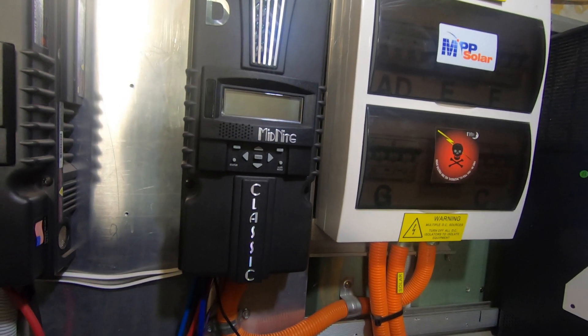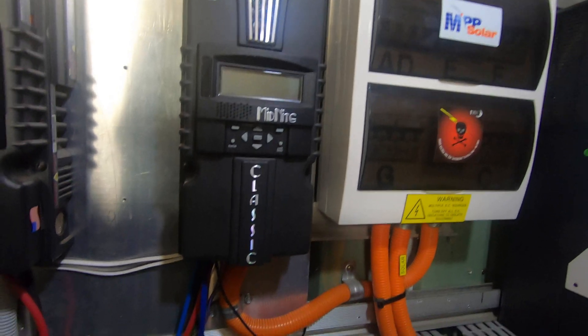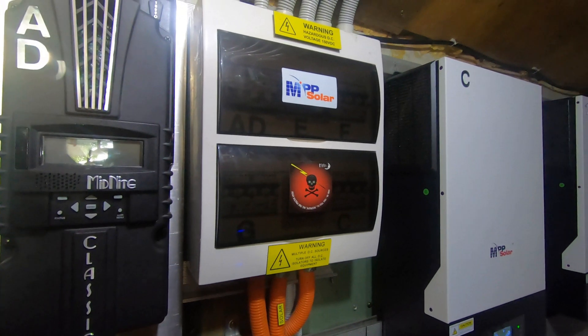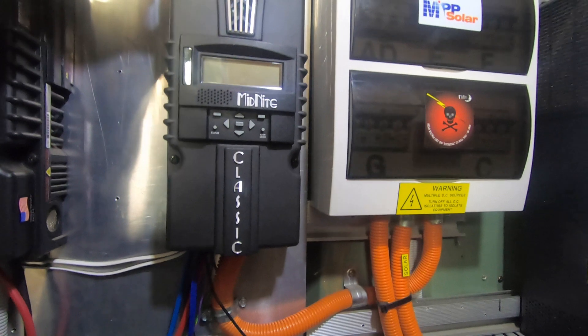It's a 98 volt DC solar circuit to a 48 volt system, which equates to 52 volts because it's charging. With the circuit breaker switched off for the solar and the fuse pulled for the battery, this unit is completely safe to pull off the wall.